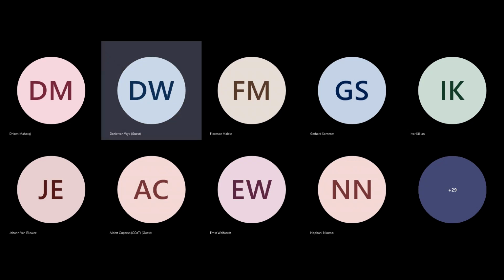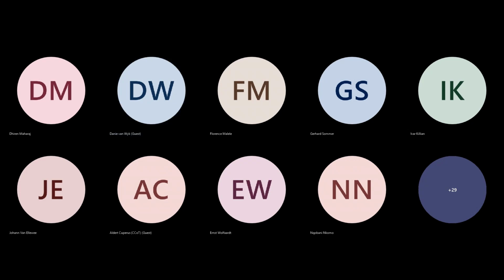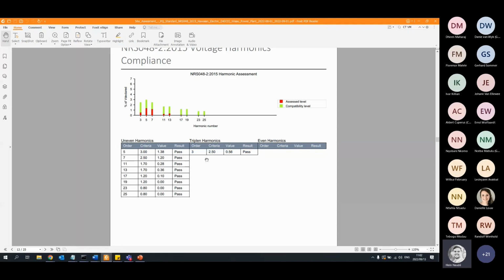In that report, on the last page, I saw triplen harmonics. What does that refer to? So, Donnie, triplen harmonics are multiples of the third. The reason why triplen harmonics get special mention is that in delta connections of transformers, triplens are mitigated because there's no neutral path for them to return on.